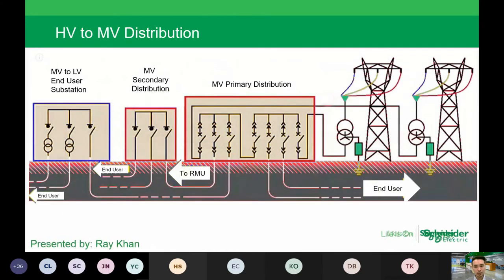This page talks quickly about the HV to MV distribution. We step down through the switchgear, and it goes out to the end user LV portion as well. It goes into the primary distribution, which uses about 22 kV, sometimes as high as 40 kV. From the primary distribution, it can also provide power directly to end customers or the customer substation. And from the primary substation, in certain projects, we branch down into the secondary distribution.